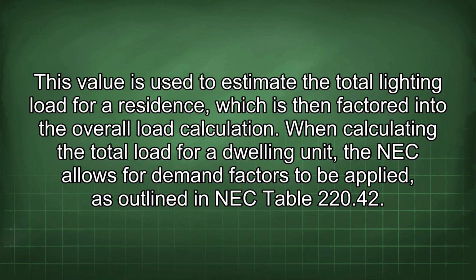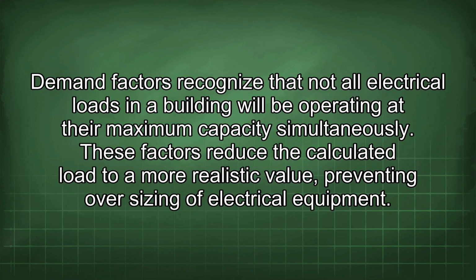When calculating the total load for a dwelling unit, the NEC allows for demand factors to be applied, as outlined in NEC Table 220.42. Demand factors recognize that not all electrical loads in the building will be operating at their maximum capacity simultaneously. These factors reduce the calculated load to a more realistic value, preventing oversizing of electrical equipment.